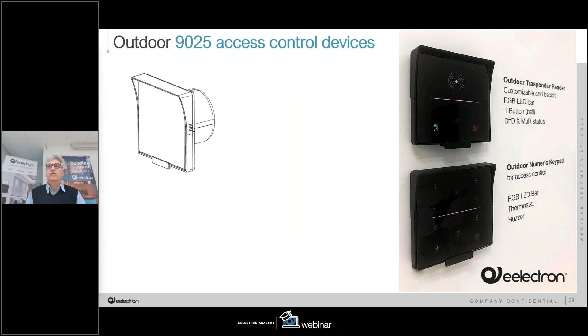Now we are introducing the outdoor 9025 access control devices. We give the possibility to install a reader or keypad outdoor with IP54 protection. If you are looking for an outdoor installation solution, you have to order a different part number. Even if the reader and keypad electronics are the same as for indoor installation, you need a special part number because the hardware is treated differently, with a special paint on the PCB to prevent humidity from damaging the electronics. So you order a different part number for the reader or numeric pad, plus the accessory, which is this cover that gives the IP54 protection.